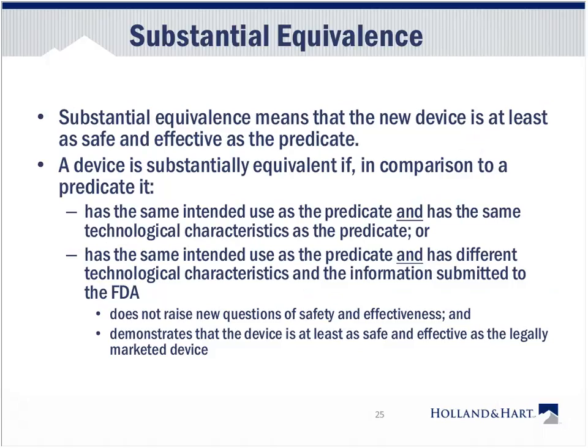So let's talk about substantial equivalence. Substantial equivalence means the new device is at least as safe and effective as the predicate device. A device is substantially equivalent if, in comparison to the predicate, it has the same intended use and the same technological characteristics, or has the same intended use and different technological characteristics, and the information submitted to the FDA does not raise new questions of safety and effectiveness and demonstrates that the device is at least as safe and effective as the legally marketed device.